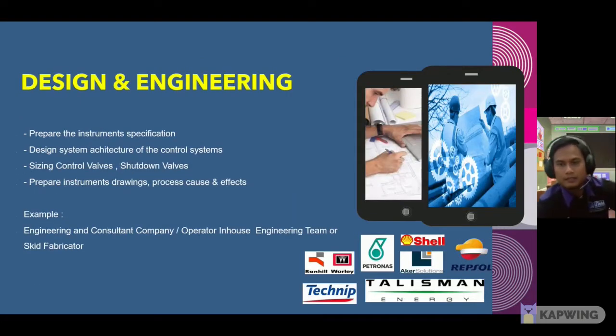And then for design and engineering, the second phase, the scope is to prepare the instrument specification and then design the system architecture of the control system, sizing control valves and shutdown valves, and preparing instrument drawings and process cause and effect. This is for engineering and consultant companies, operator in-house engineering teams, or skid fabricators. Example companies that take this job are Petronas, Shell, Repsol, Technip, Talisman Energy and more.